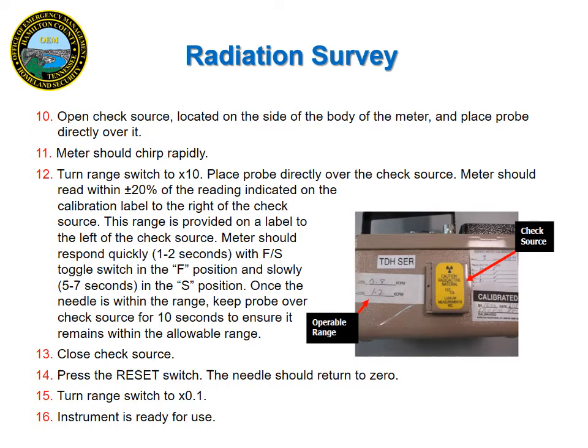So to do the operability check, you will need to open the check source door on the side of the monitor. This is that little yellow door on the side. There's a small radioactive source behind the door that you can use to ensure that the monitor is working correctly. So after you open that door, place the mesh side of the probe against the source. The monitor should begin to chirp rapidly.